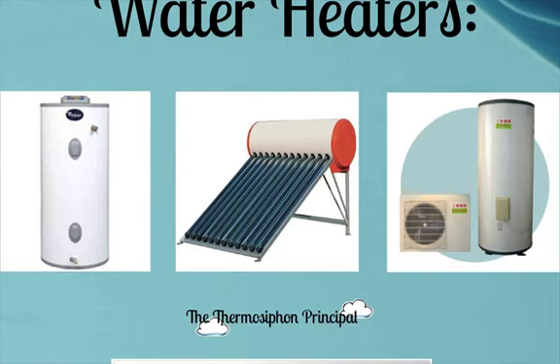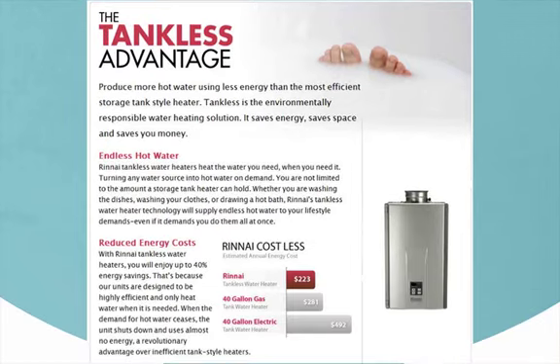Now, the one that you see on the far right is what's called a heat pump water heater, and it takes excess heat from air in hot places like in a kitchen or in a mechanical room, and then it dehumidifies the air and uses it to basically heat a storage tank water heater. A really great option now are these tankless water heaters, and they use a really large amount of heat but for a short period of time to heat a limited amount of water. Essentially, they're usually installed at the fixture, so when you turn on the shower, intense heat will heat that water, and then it'll stop heating it when you're finished. So you save a lot of energy costs because you're not heating water that you're not using, like you do in a storage tank water heater.